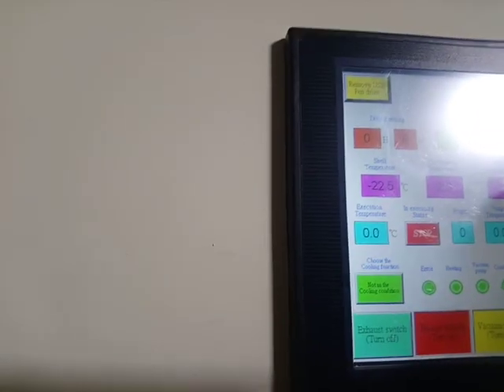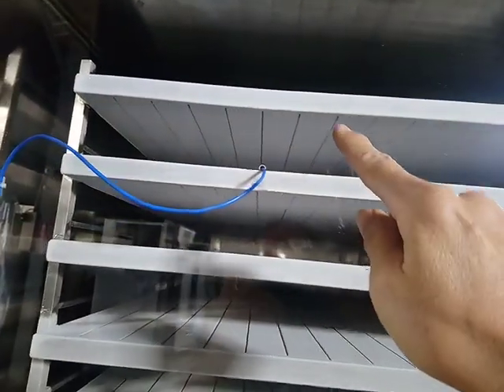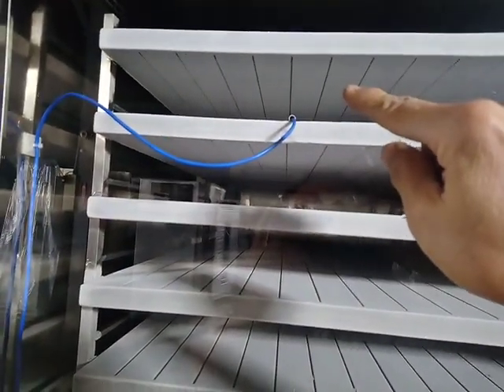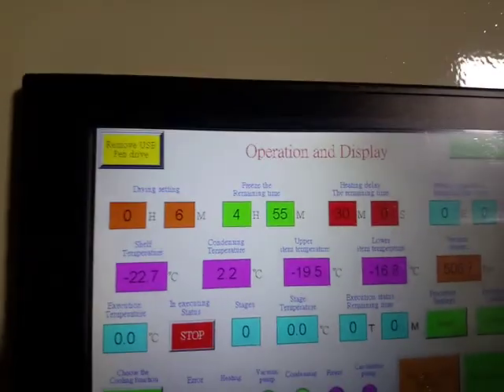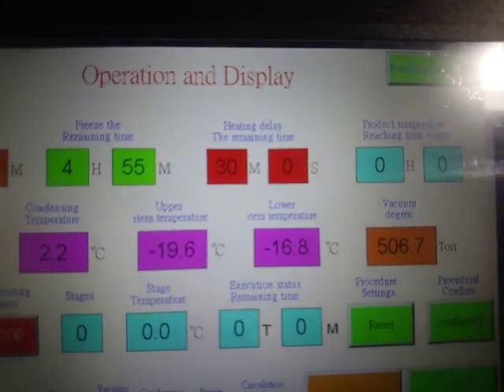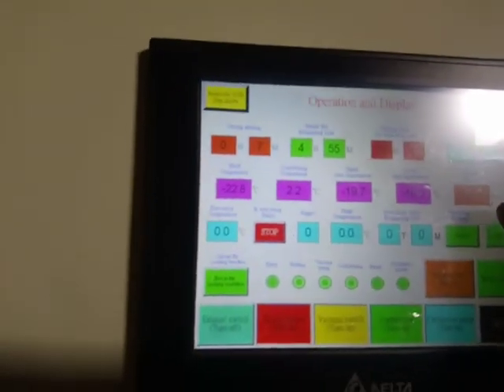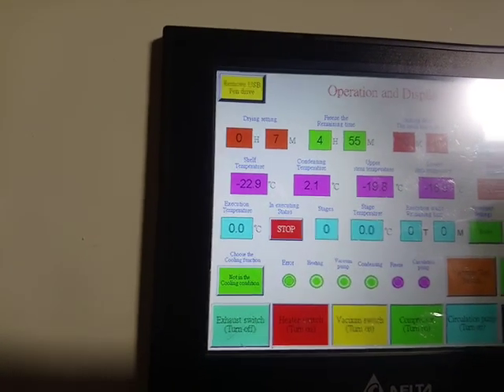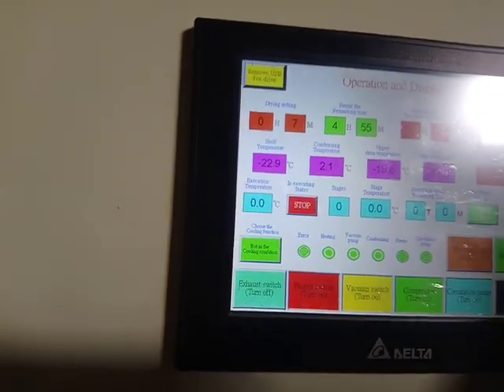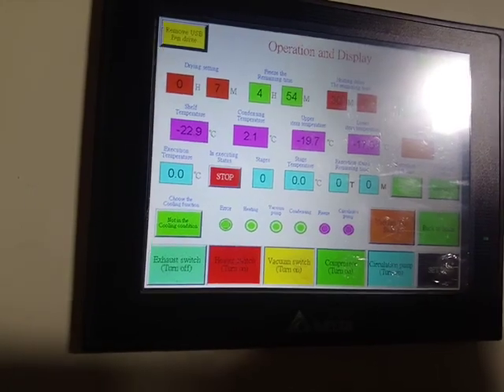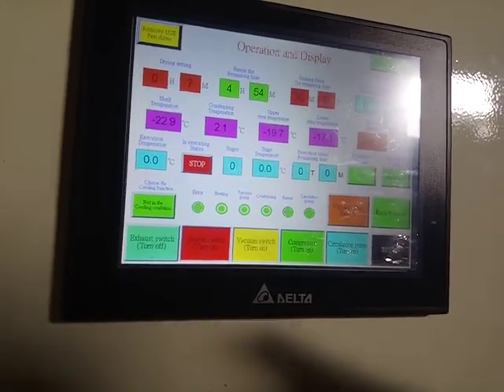And the upper item temperature is here. We have two sensor probes, one up here and one down here. So you insert the two item temperature sensors. And the lower item temperature is here. And the vacuum degree right now is 500.6. It needs to go down low to maybe minus 3 or minus 2.